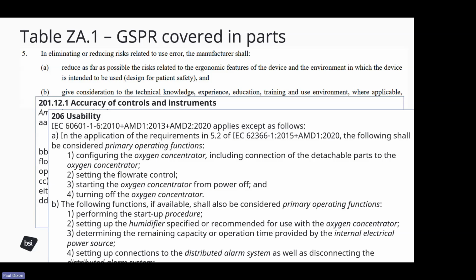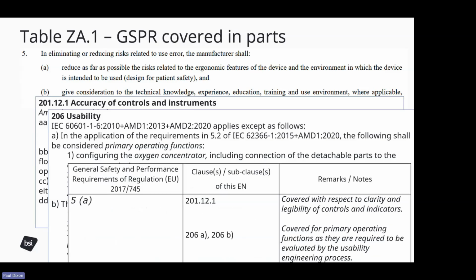Because these are listed as primary operating functions, the test report will demonstrate that these have been through valid human factors validation, and therefore we can justify use of clause 201.12.1 for the clarity and legibility of controls, and we can use the subclauses within 206 for the primary operating functions because they are required to be evaluated by the usability engineering process, and that was accepted by the assessors.